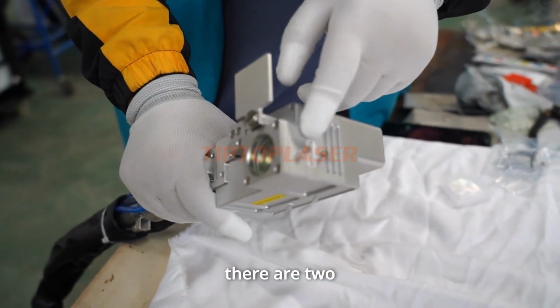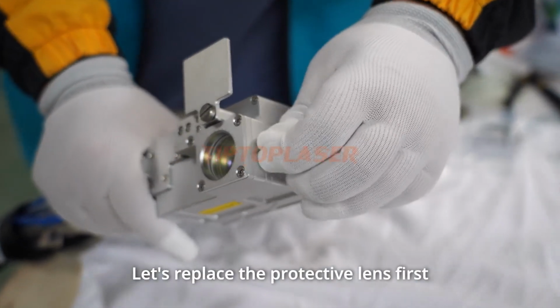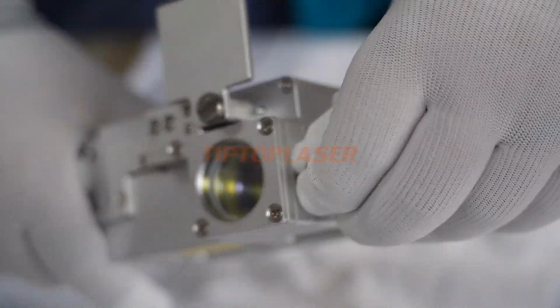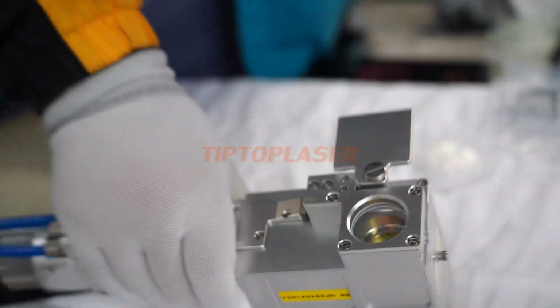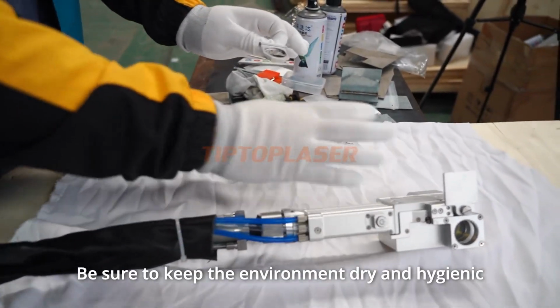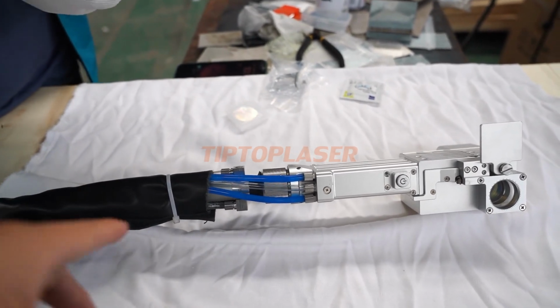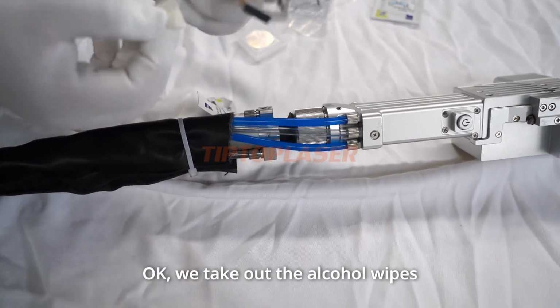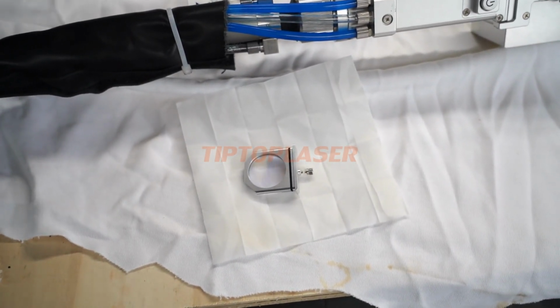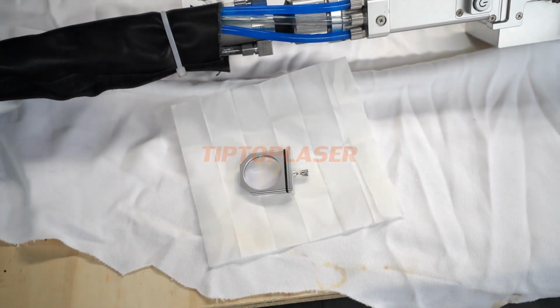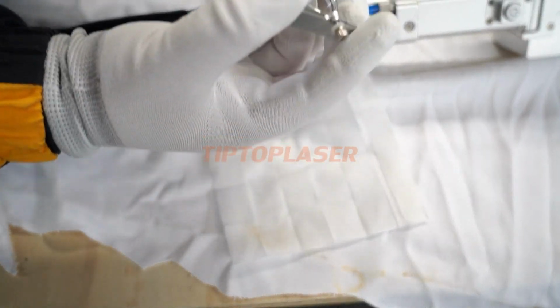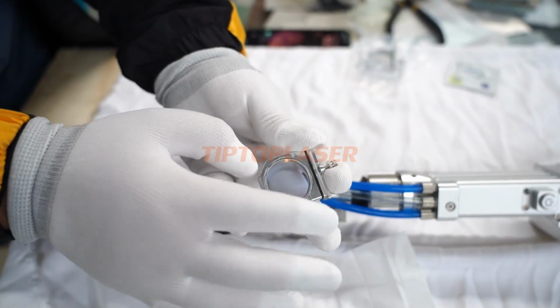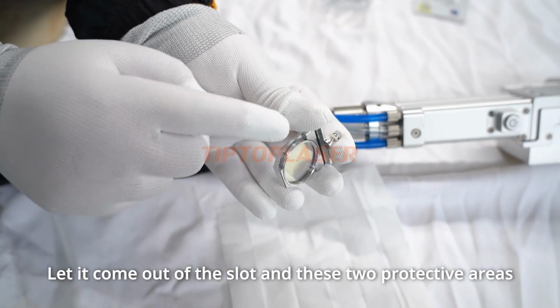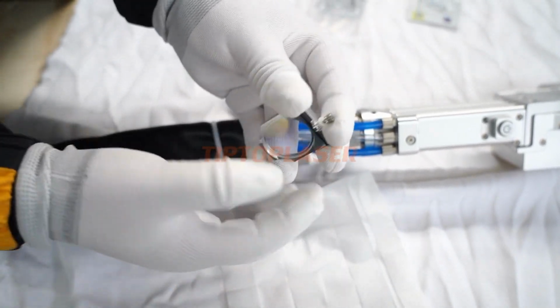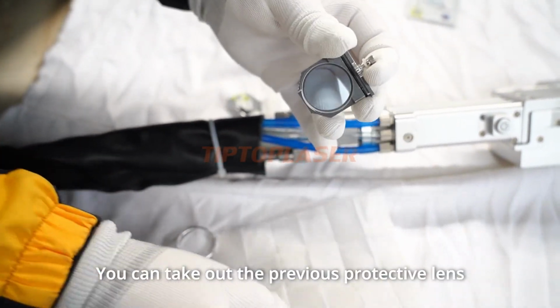When replacing, there are two. The first one is the outermost one, which is the protective lens. The focusing lens is inside. Let's replace the protective lens first. Take off the protective lens. Be sure to keep the environment dry and hygienic. We take out the alcohol wipes. Put the removed protective lens on the alcohol wipes. Avoid contamination. Take out the new protective lens, then install it on top. Turn the paddle of this circle counterclockwise. Let it come out of the slot and these two protective areas. You can check it out. You can take out the previous protective lens, then replace it with a new one.